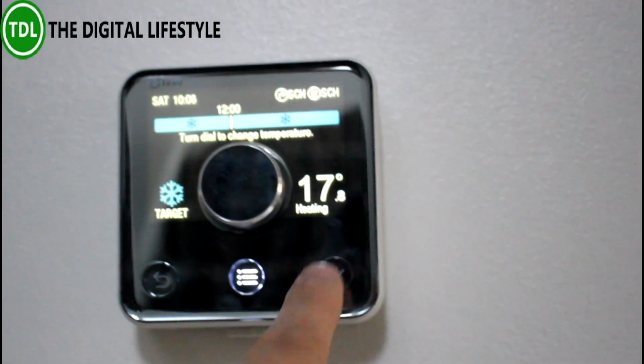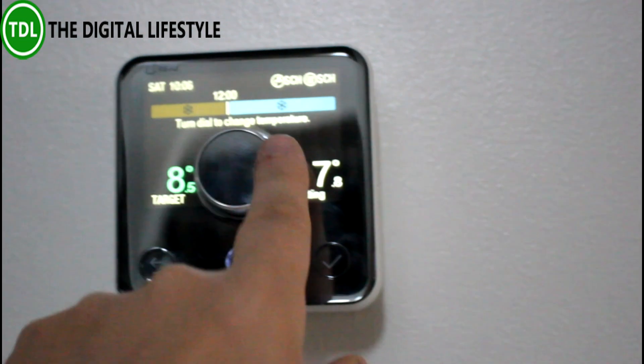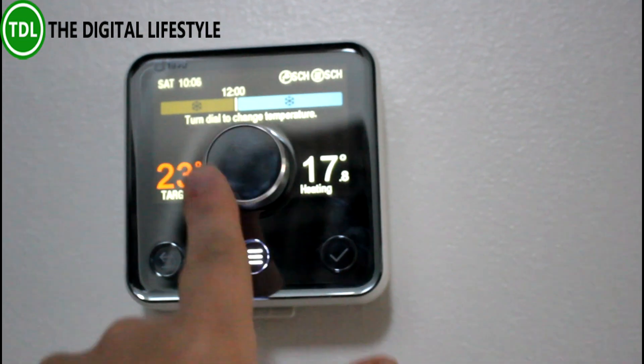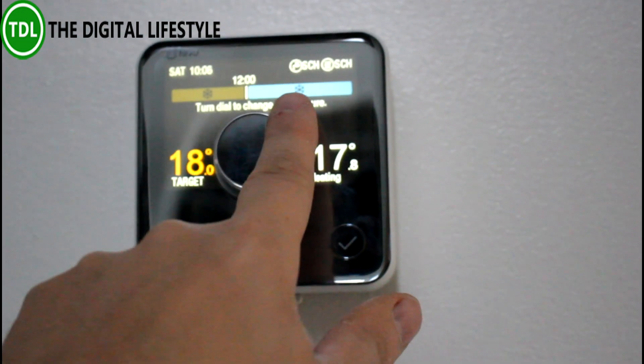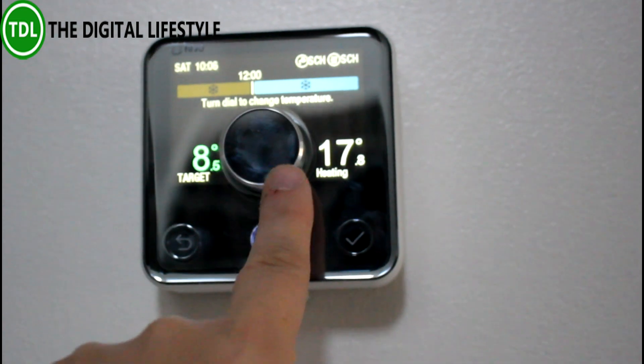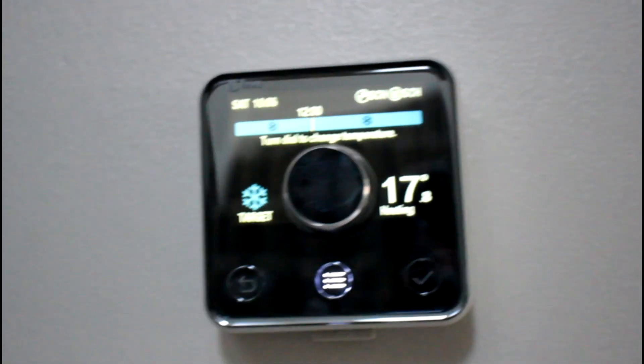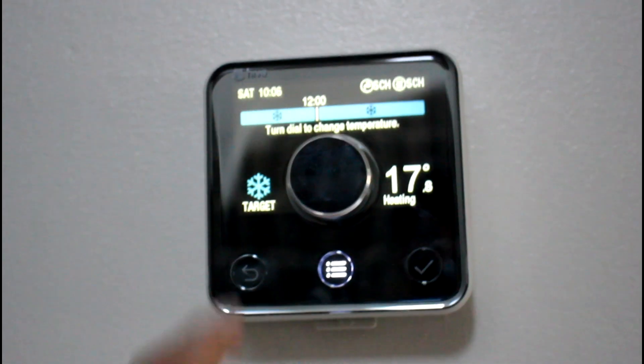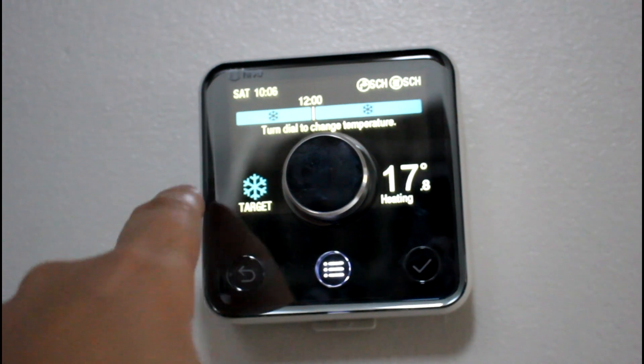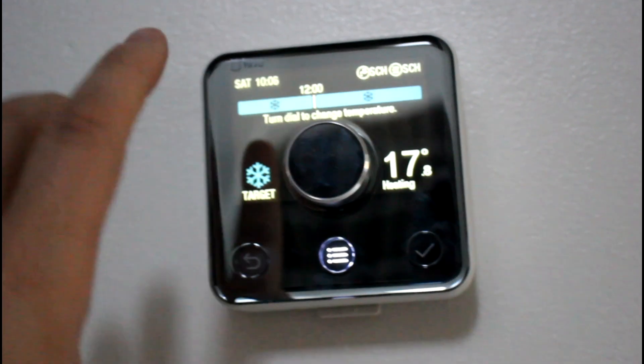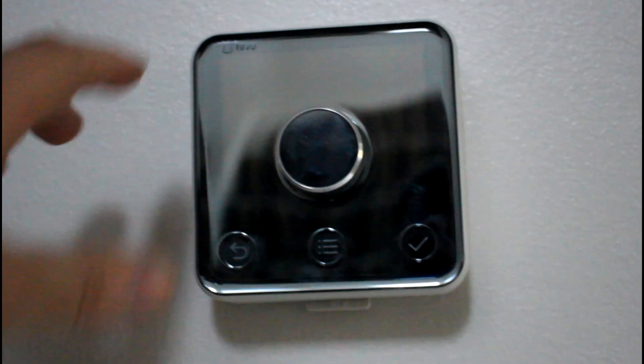This is what's detecting the temperature. From here you can control everything. You can see the current temperature. It's off at the moment, but I can select the target temperature. I can boost the heating if I wanted to. That's showing that if it gets to seven degrees, it'll turn the heating on regardless of what programming I've got set, so it effectively stops your system freezing.